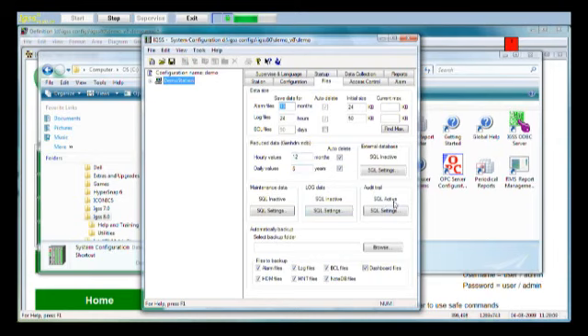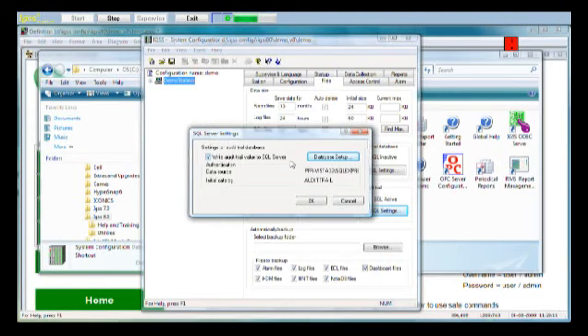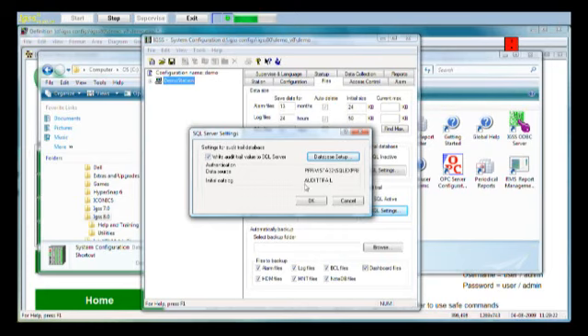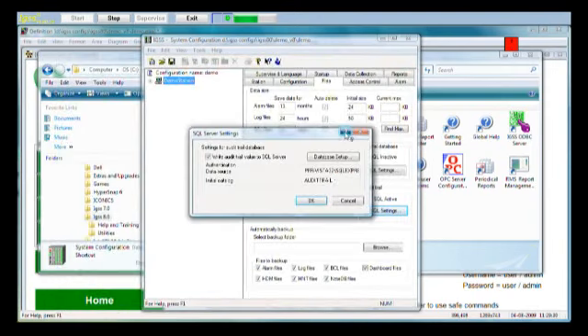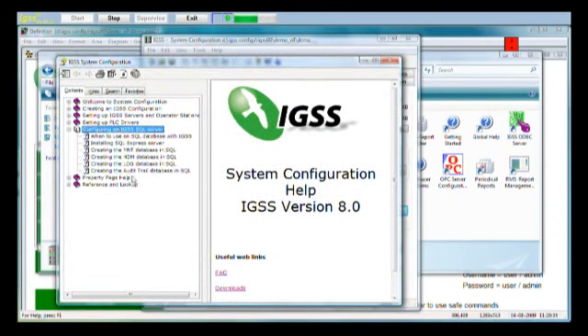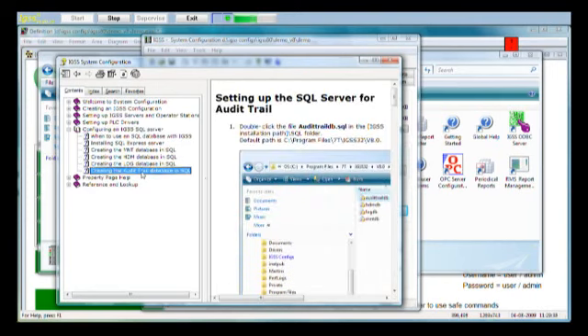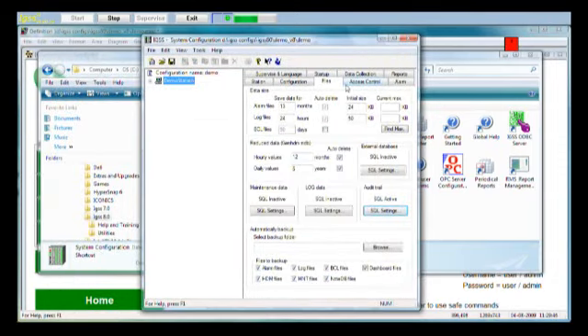Audit trail, and it says SQL active. So it saves all its data in an SQL database, but of course this SQL database must be set up first. SQL settings. This is my current setup. As you can see, I have data source, that's my computer name slash SQL Express. Initial catalog is audit trail. And this is very easy to set up because we have included an SQL database file. If you click on the question mark here in this dialog box, click on the button, go to configuring an IGSS SQL server, creating the audit trail database in SQL, then it takes you through all the steps in setting up audit trail.